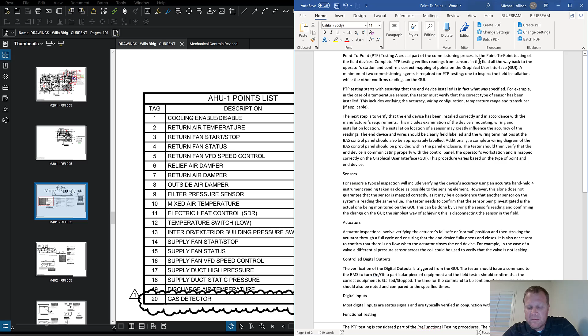Well, generally you'd have to have the air handler started and running, kind of. And then you could start to see if the return air temperature sensor is actually reading. And is it reading correctly? And maybe there's a couple return air temperatures. What if the, let's see, return mixed air temperature. Okay. Number 10 and number 2 are both reading temperatures, and they're just little tiny wires. And so kind of the point of point to point is to make sure that, one, somebody hasn't messed up, to see if the wrong sensor is being read, or is the sensor reading correctly?